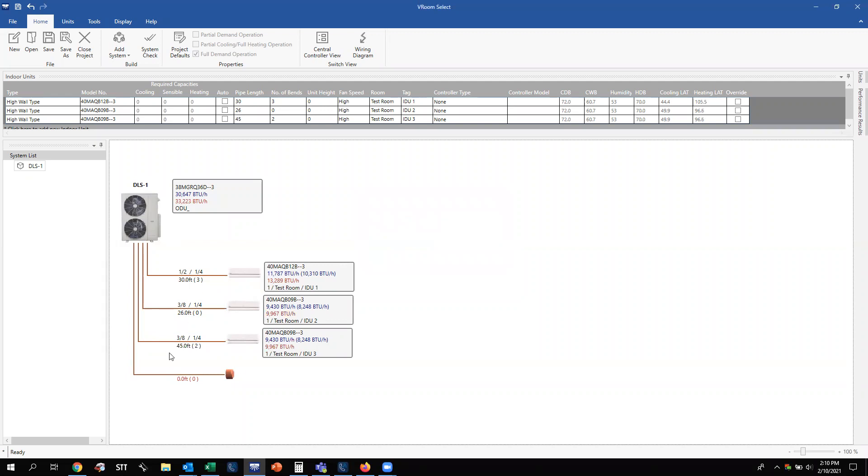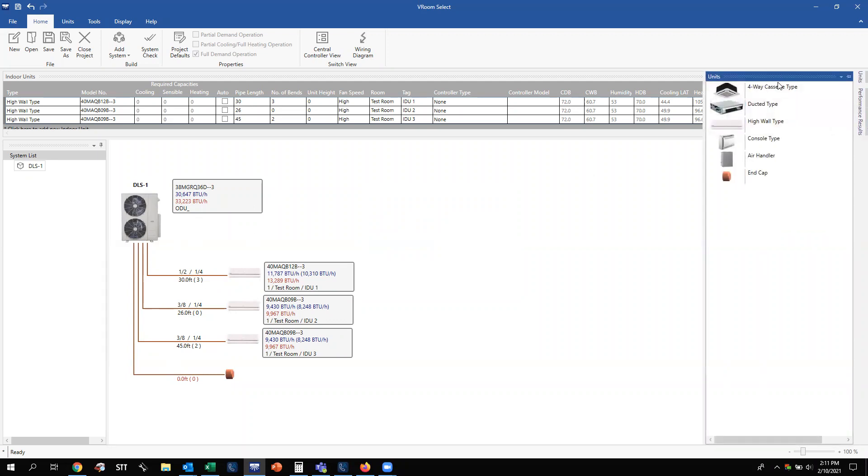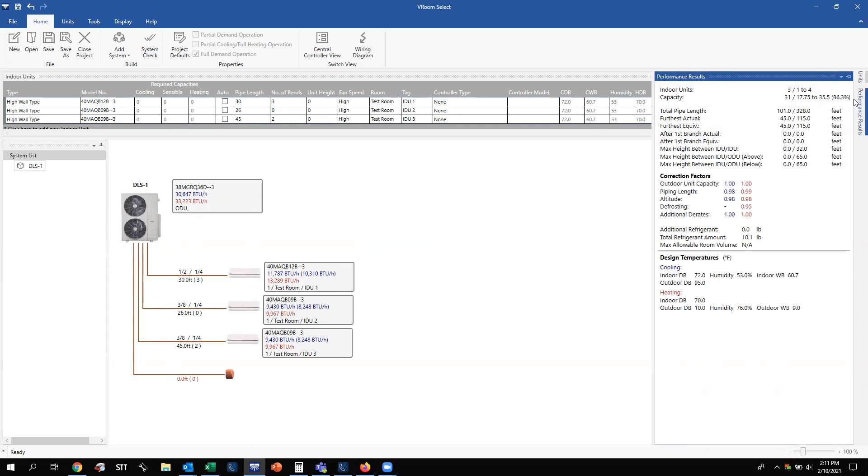Once you have your piping lengths entered, go to the right side of the screen where you'll see two tabs. Under the Performance Results tab, you have your maximum total piping length, vertical height allowances, and all the intricacies of piping rules for both ductless and VRF systems — showing what you currently have on the system and the allowable limits you cannot exceed. Most importantly, this tab shows your additional refrigerant amount and total refrigerant amount. If you haven't exceeded the threshold for a multi-zone system, the refrigerant charge in the outdoor unit is sufficient for the system.